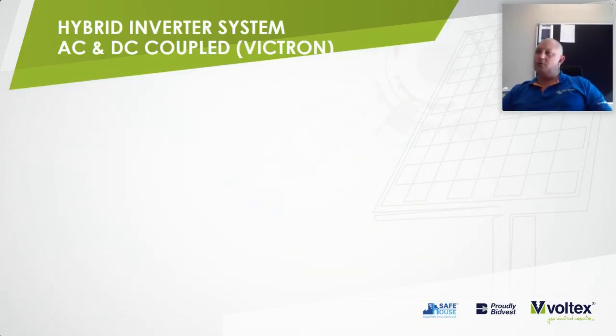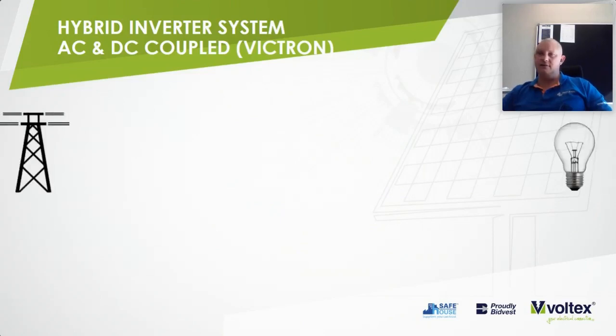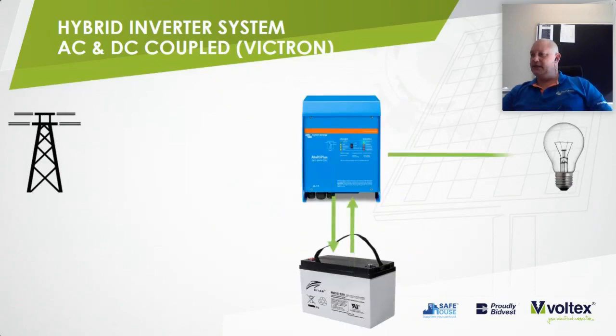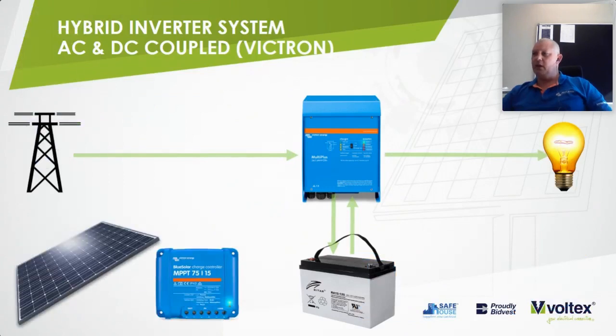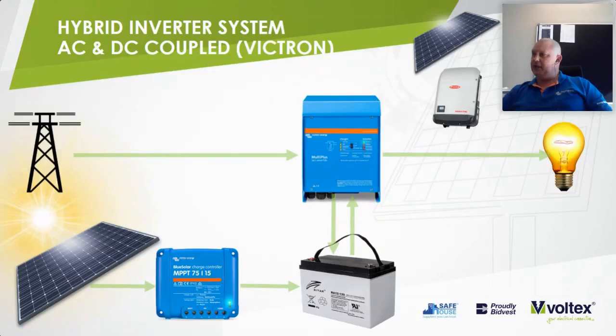So the combination of these systems is intended for larger type systems, deemed very effective, where you need a specific amount of load that needs to be covered, and you've got a specific backup that you need to cater for. So the basic setup remains the same. The inverter and battery connection is still there. Your DC coupling takes place by adding an MPPT charge controller to the equation.